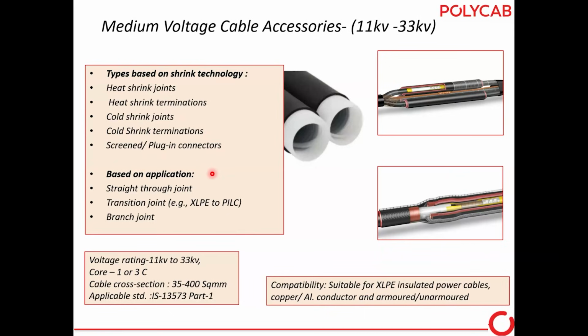Based on applications, we classified straight-through joint, transition joint, and branch joint. Transition joints we use wherever PILC to XLPE joints are required. Voltage rating 11 kV to 33 kV, core, single core, 3 core. Cable cross sections we use 35 to 400 square mm. Application standards are IS; these cable accessories are as per the IS 13573 part 2, or testing as per part 2.